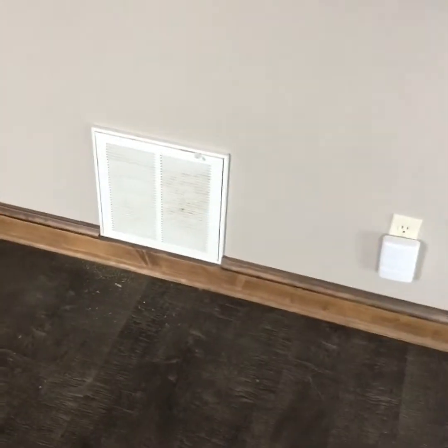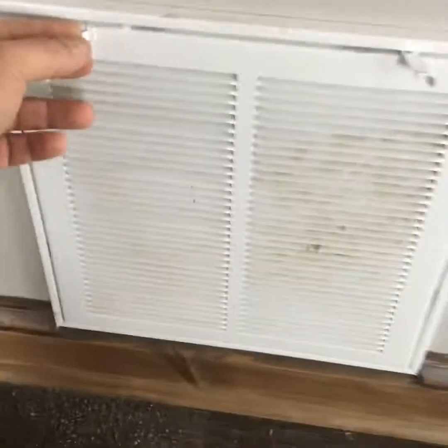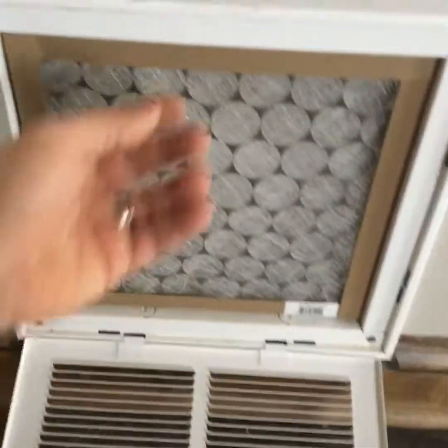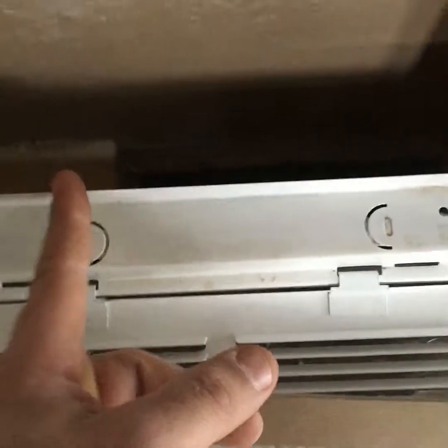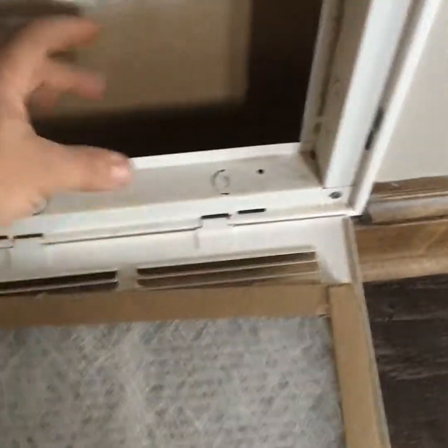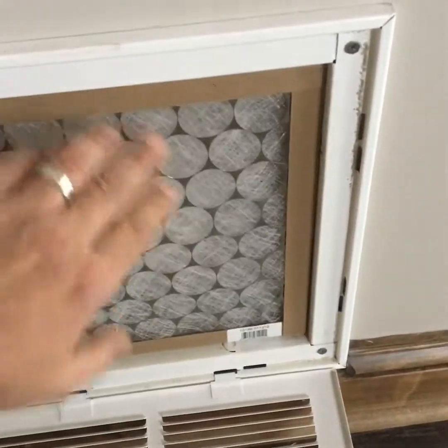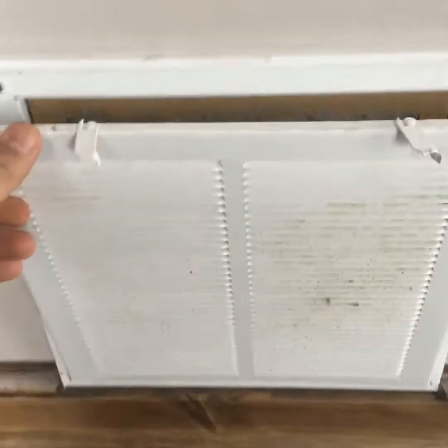The original return system in this house had 3 of these 12 inch by 12 inch filter back grills. What they did is they just put these straight into this wall cavity, and then they cut out the floor plate. It's probably about 7 inches by 3.5 inches. That's one of the 3 returns. All of them are about the same for a 3-ton system.